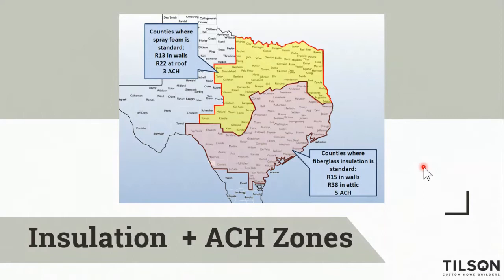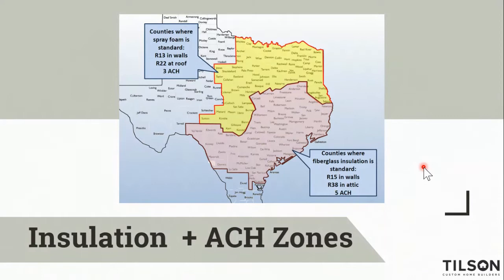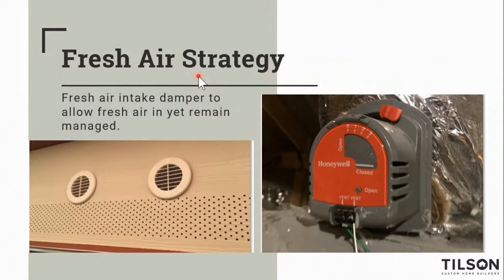Testing is really important for insulation and air changes per hour. In climate zone two down here, we're doing R15 batts in the walls and R38 in the attic, and we have to achieve five air changes per hour or less. Up in the yellow on screen are counties where we're going to be doing spray foam as standard — it's not required, it's just what we do standard. You're going to have open-cell spray foam insulation that helps us achieve three air changes per hour or less.